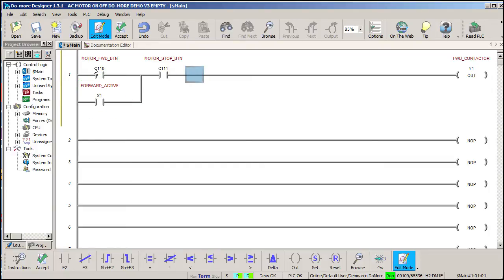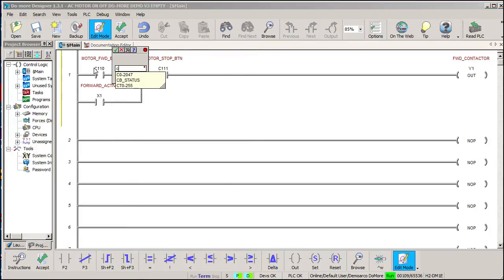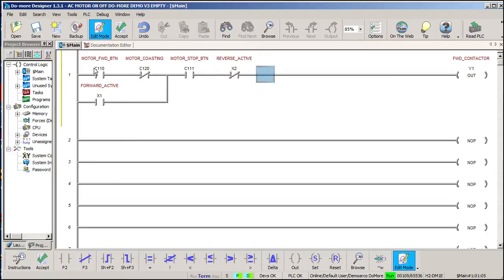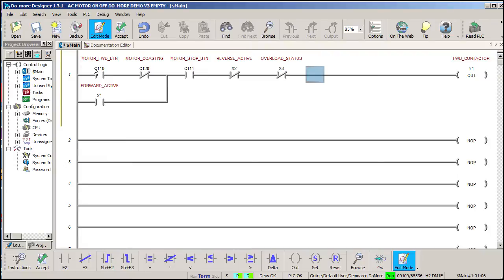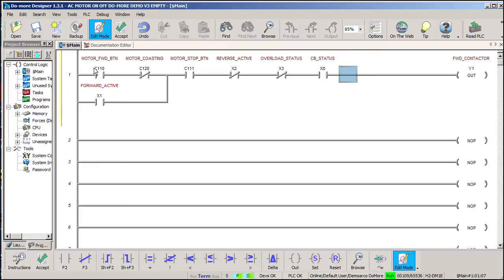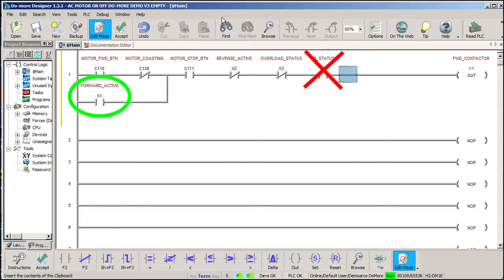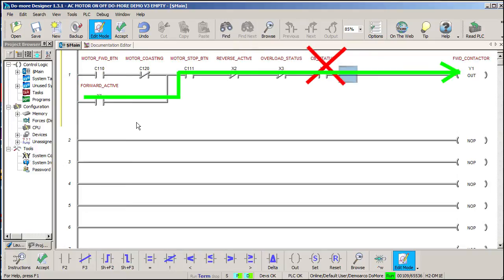We only want the motor to be started if the motor is not coasting – we'll create that in just a minute – and we want to make sure that the reverse contactor is not engaged. We don't want to run the motor if the overload is tripped. And finally, we don't want the motor to be enabled if there is no power. This serves as a handy reminder to check the power of course, but more importantly it makes sure the motor can't be latched or sealed in while the power is off. If we didn't check the circuit breaker status, then there is nothing to prevent this ladder code from energizing the contactor which enables the AUX contact and latches or seals in the circuit.